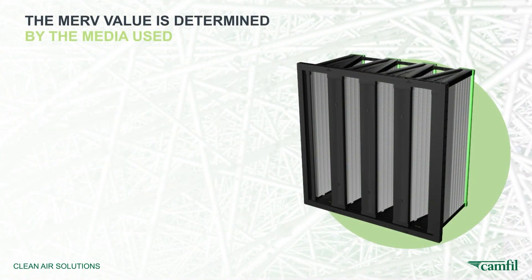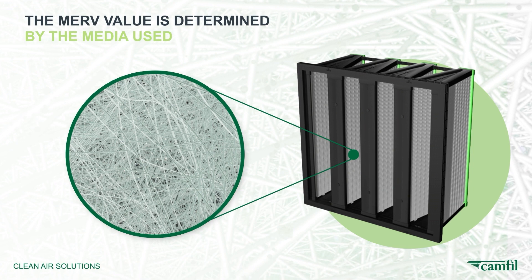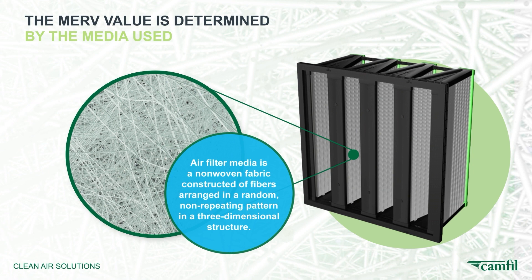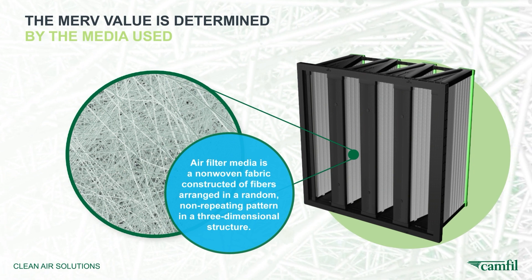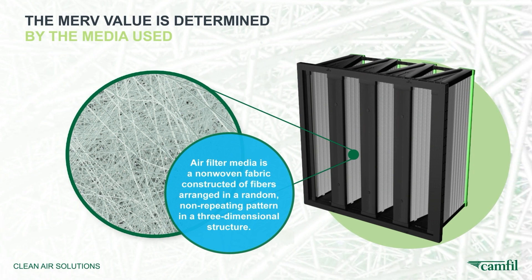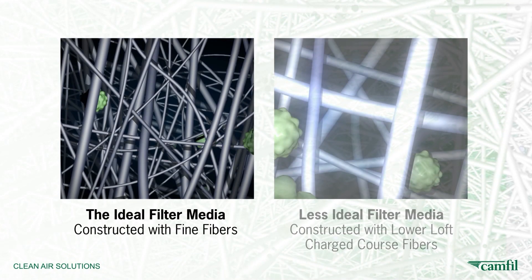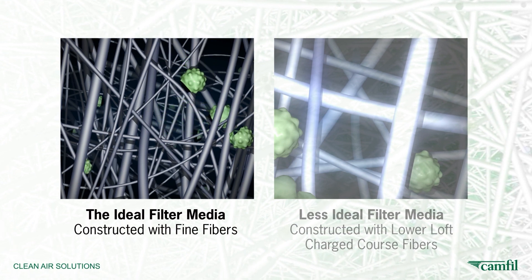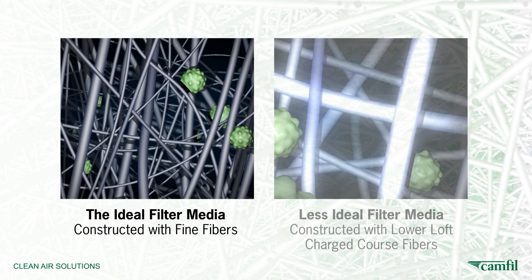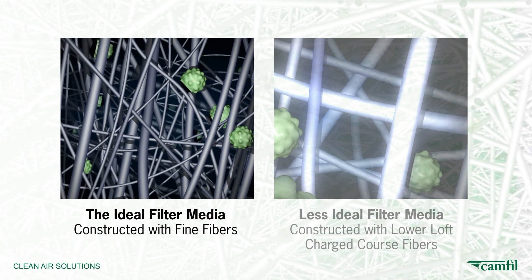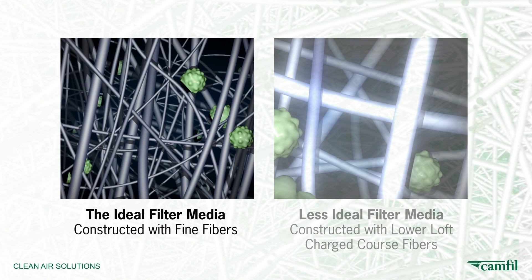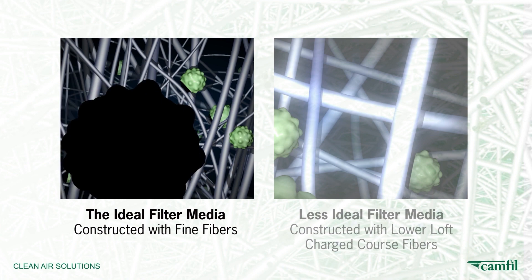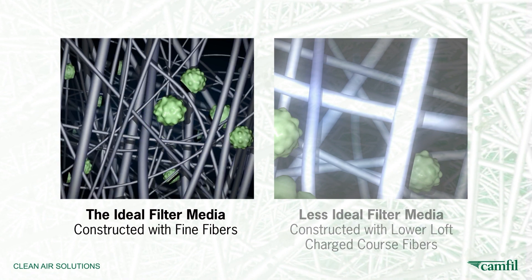The most important component in determining the MERV value of a filter is the media. Media is the name given to the fabric-like portion of an air filter that is configured within the frame that supports it. There are two primary types of media used in the filtration industry. The ideal filter media consists of a large number of fine fibers in a confined space, constructed as a non-woven fabric. Filters utilizing this type of media capture particles through mechanical principles which do not degrade over time. This is the ideal media type to ensure efficiency for the entire service life of the filter and maintain compliance with ASHRAE 170.